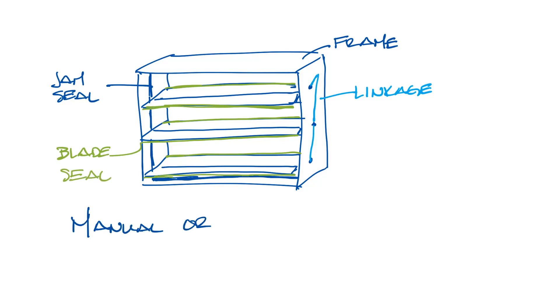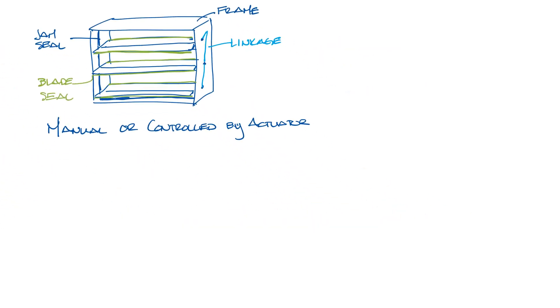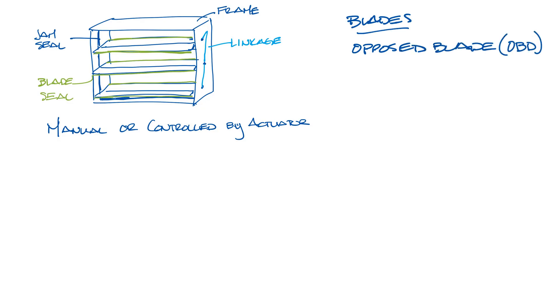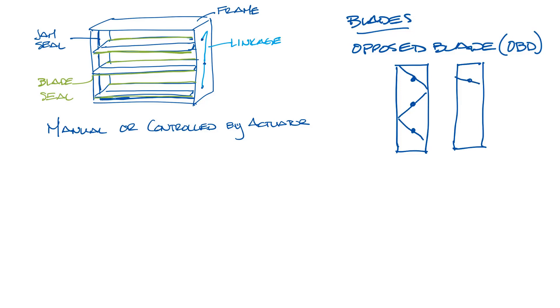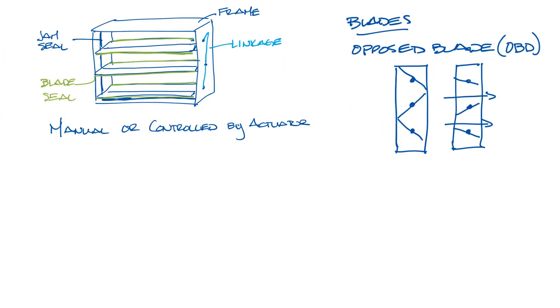Dampers can be manually operated or controlled by an actuator. Now let's look at different types of blades. First of all, dampers can have opposed blades, where each blade moves in the opposite direction of the blade next to it. The benefit of this is that the air moves pretty much straight through the damper regardless of the position of the blades, giving you good uniform airflow leaving the damper.